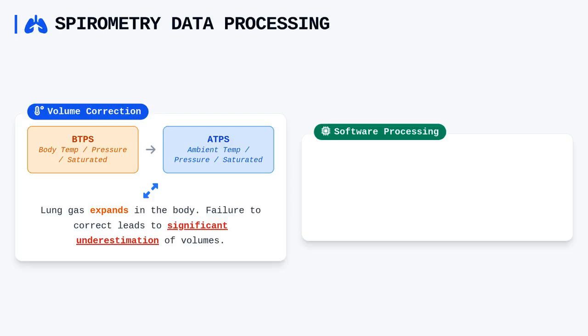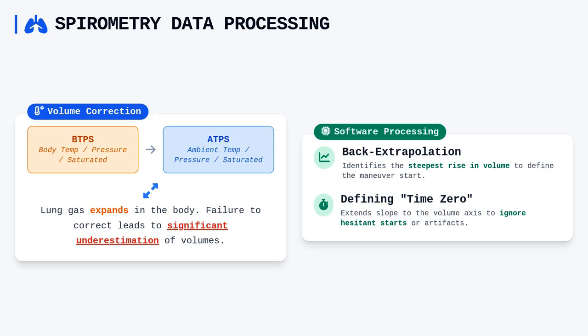Furthermore, software-level processing, such as back extrapolation, is essential for defining the start of a forced expiratory maneuver. By identifying the point of steepest rise in volume and extending it back to the intersection with the volume axis, we can determine time zero, effectively ignoring hesitant starts or minor artifacts during the initiation of the test.